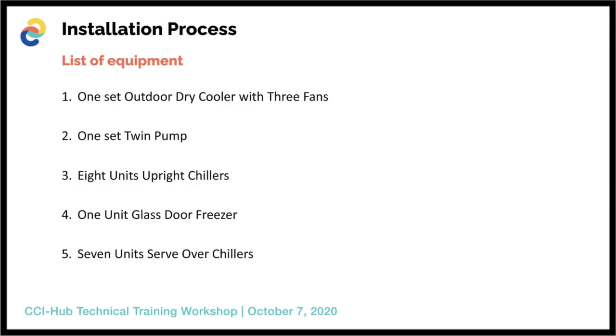Next is the list of equipment. First, one set of 3-fan outdoor dry cooler. One of the major parts of the Waterloop system is the dry cooler, which serves as heat rejection equipment. It blows away the heat circulating inside the stainless pipes. We used an 80 kilowatt capacity Güntner dry cooler for this project. Taking into consideration for calculating the capacity is the ambient temperature of 38 degrees Celsius and relative humidity of about 18%. Another major equipment is a set of twin pump. A pump station with two units of pump is primarily set to have a continuity of operation if one of the pumps has a problem. So we use a set of 1.3 kilowatt each Grundfos brand pump for this project.